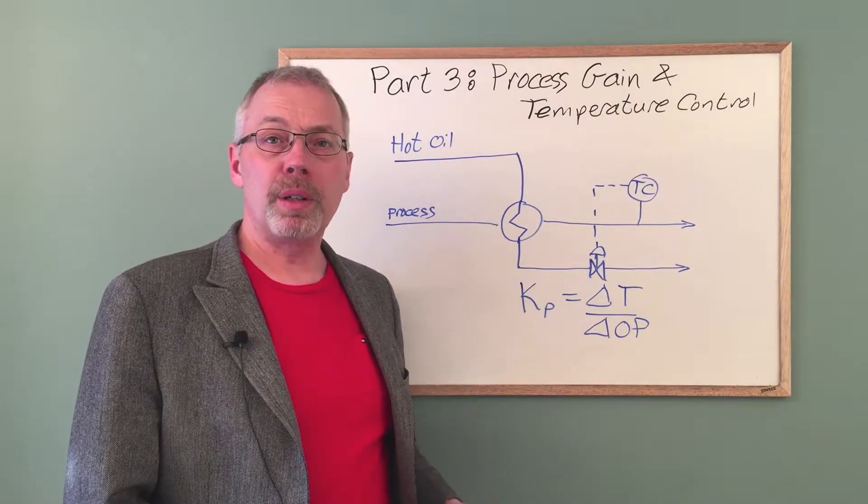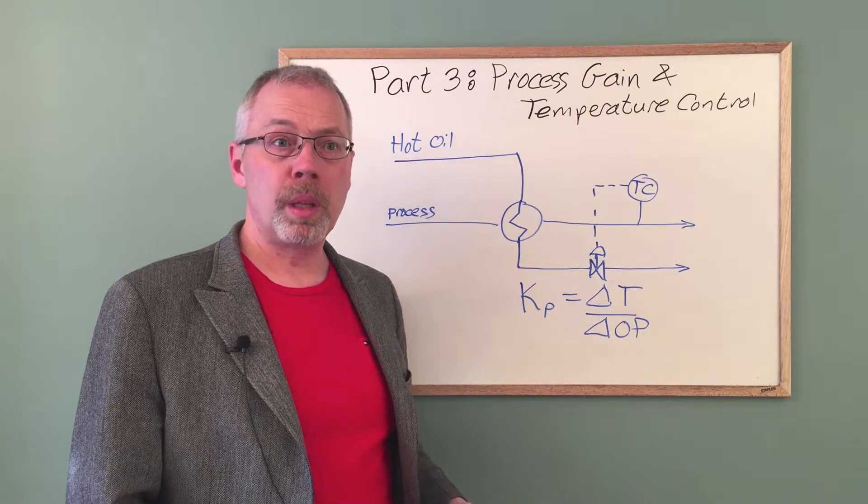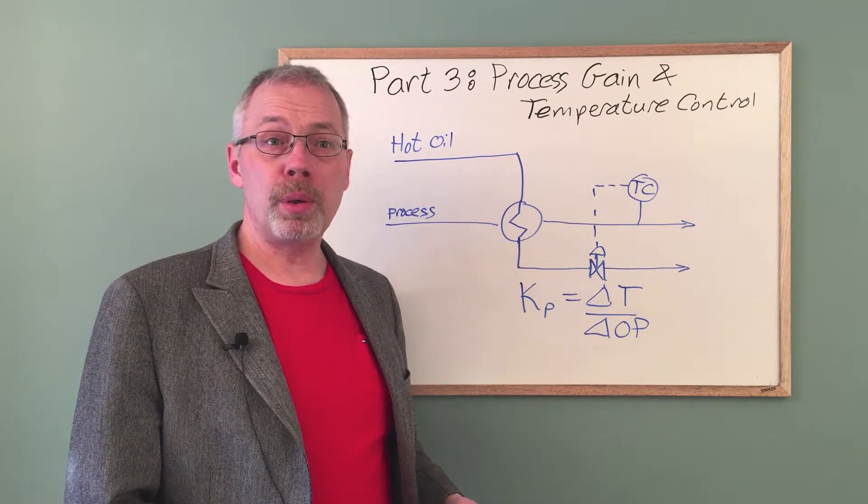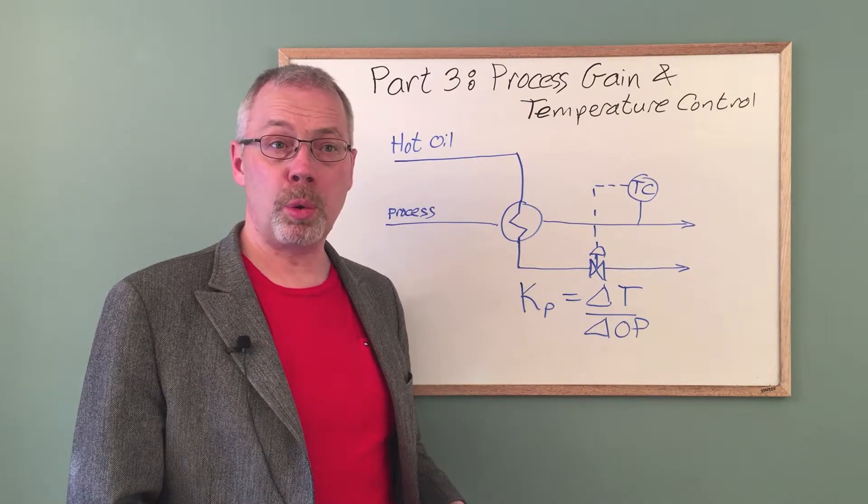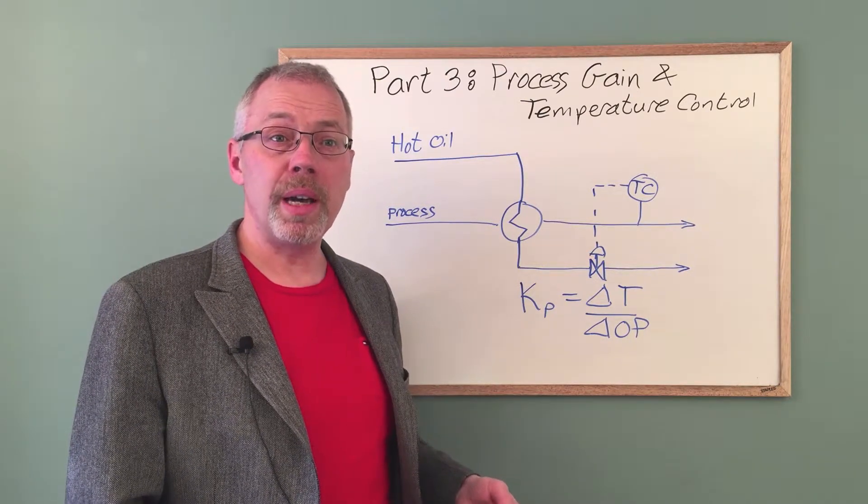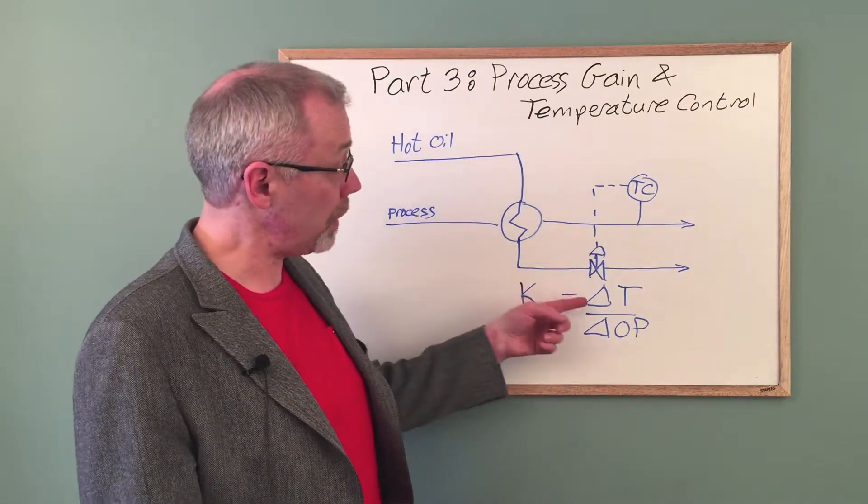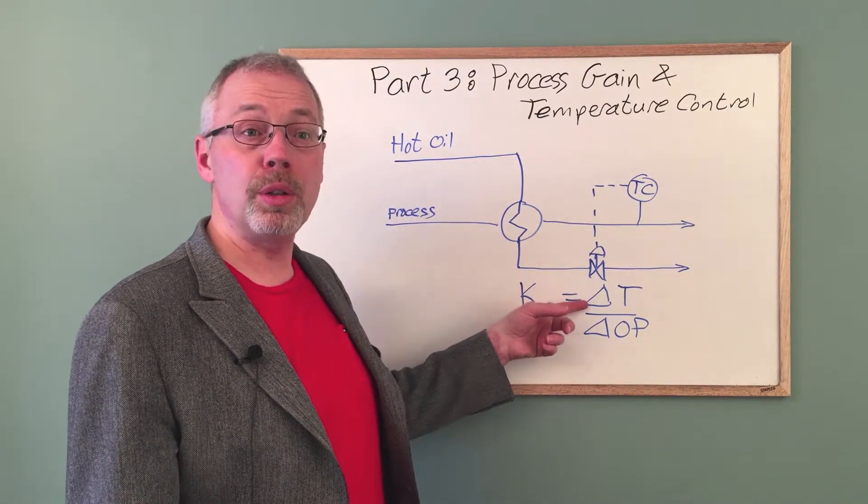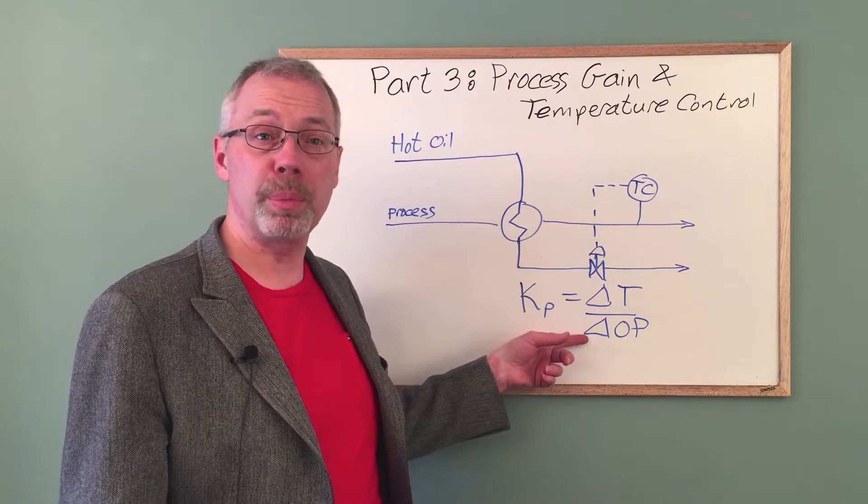This is a schematic for a typical temperature control loop. The objective is to hold the process temperature on set point by adjusting the control valve that supplies hot oil. Process gain defines how sensitive the control objective is to a change in the controller output, or valve position in this case.